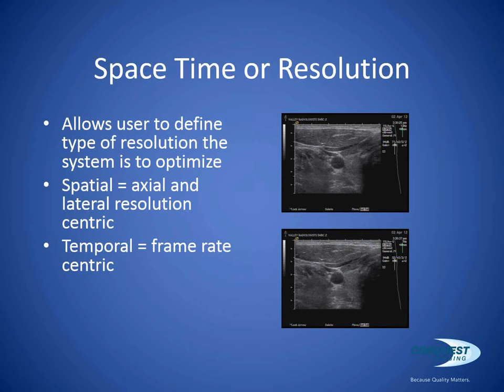If you look at the top image, it looks very grainy. This is an Acuson Sequoia, this particular image on my thyroid, and I'm using what's called a T1, or temporal 1. So that's a high frame rate. On the bottom one, I'm using what's called S2, or spatial 2, which is, I told the system I want to concentrate solely on spatial resolution. And you can see that the image is much tighter. The grain is much finer.